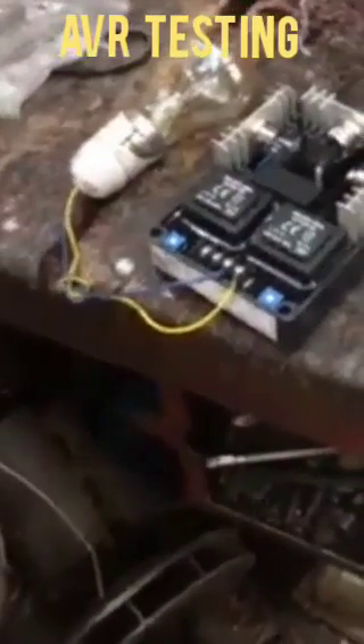Today's episode is about how to check if the AVR is okay or not. We have a connection of the AVR from the alternator — F1 and F2 — and we connect one bulb from the other two wires. We can then adjust the voltage from the voltage pot.